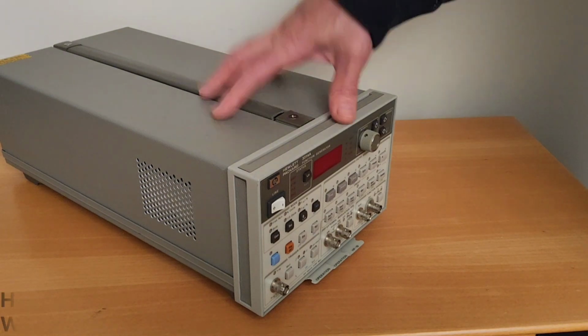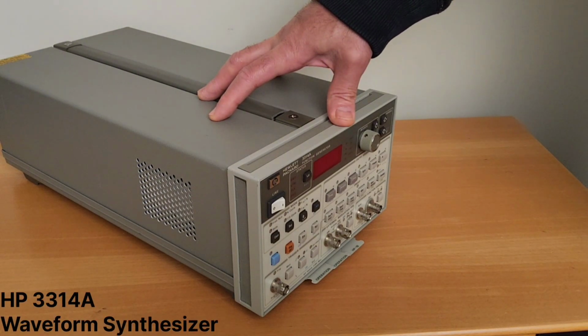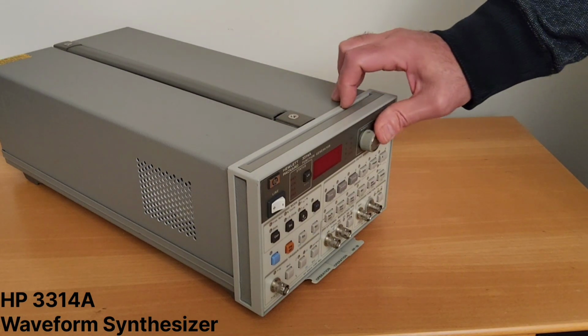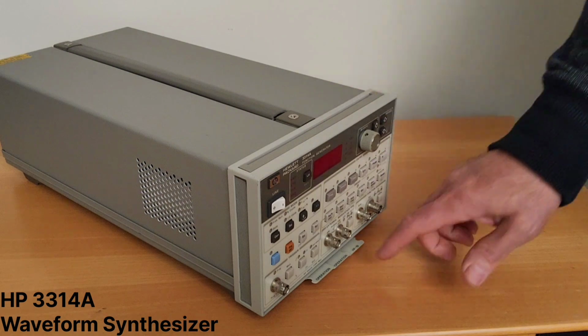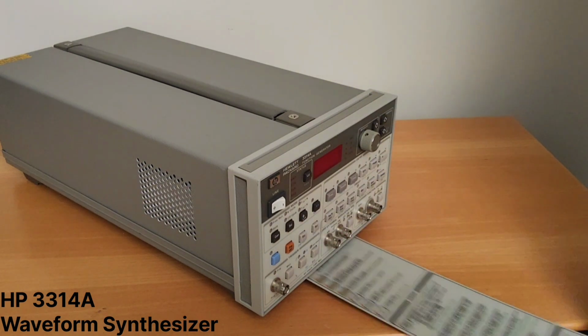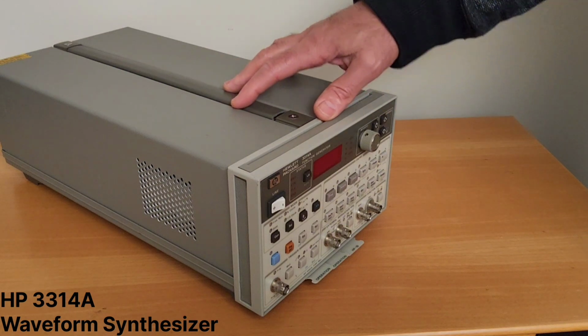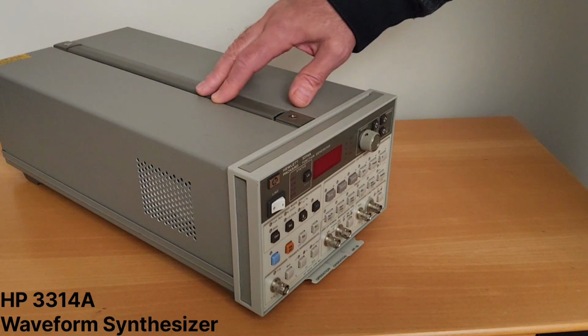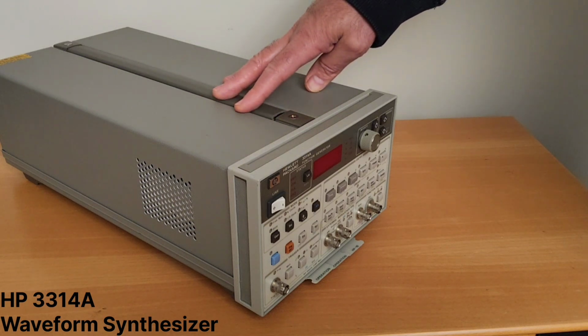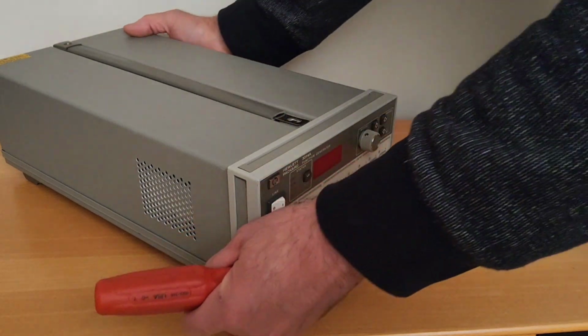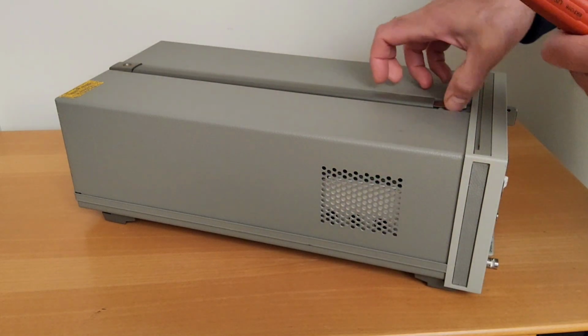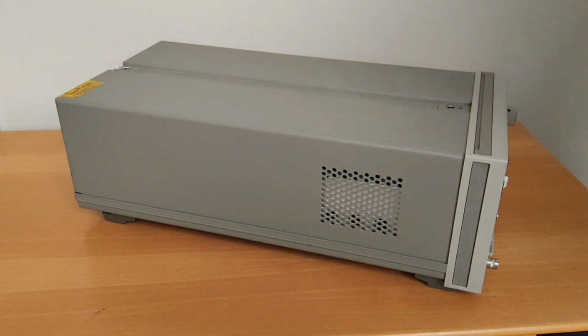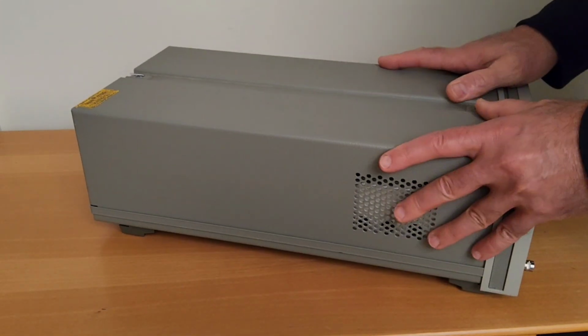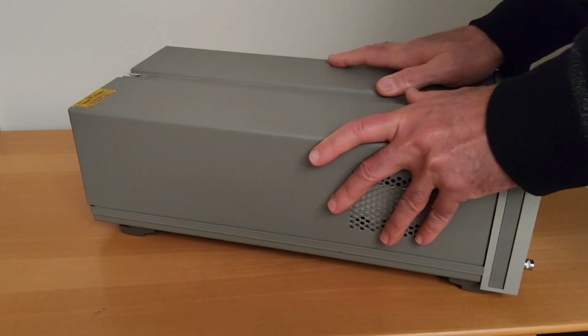All right, so moving on to the next unit, the HP 3314A. Older technology, but it seems to be in pretty good shape physically. Still has the quick built-in reference cards attached. We're going to go ahead and take the 2 screws holding the handle in place off in order to take the cover out to have a look at the condition inside. The rear bracket comes off by tilting it upwards. And now with the 2 top screws removed, it's just a matter of pushing gently on the top cover. There you go. And it comes right out.